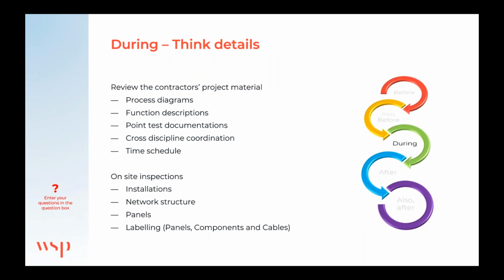During the process, many things happen automatically, but there are a few things you need to check along the way—function descriptions and cross-discipline coordination. Is what the ventilation contractor is installing the same as what the BMS contractor is actually controlling? There can be a lot of changes during a project, and you need to stay on top of this. The time schedule changes constantly, so you need to know what's going on.